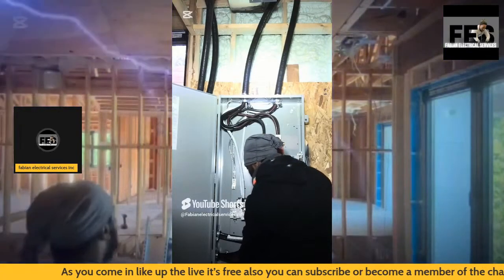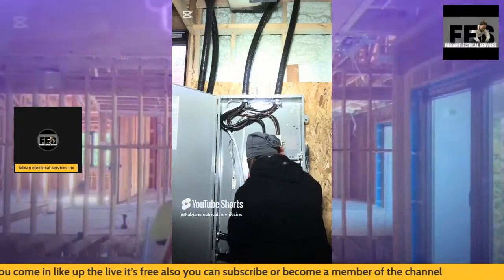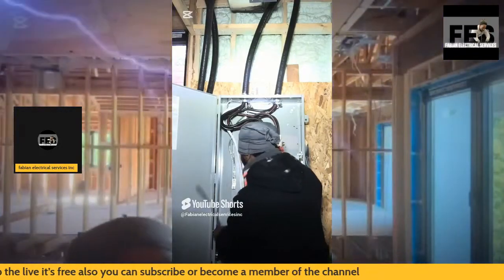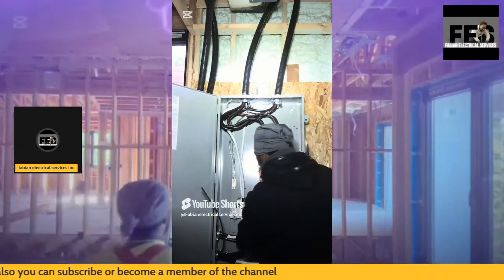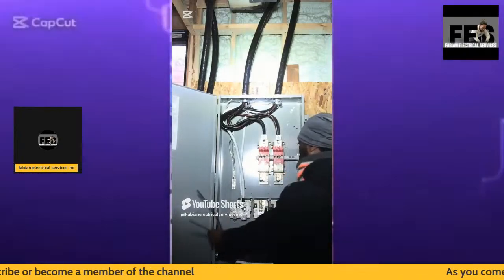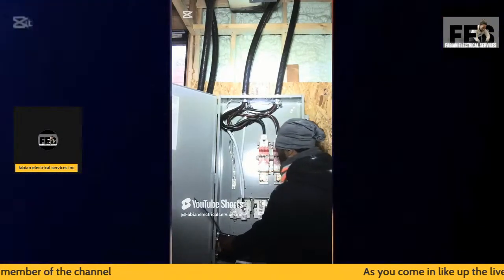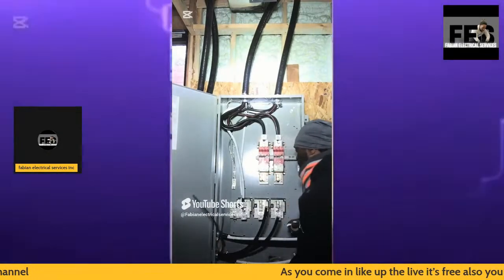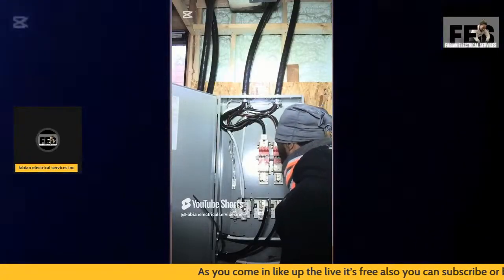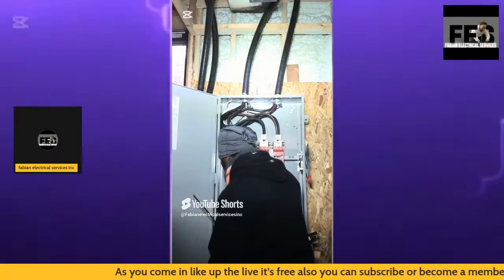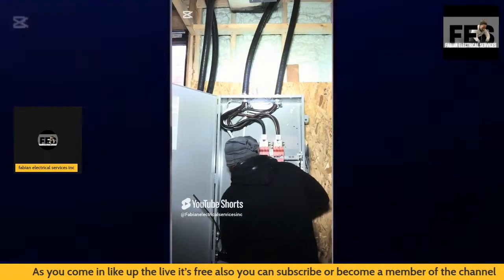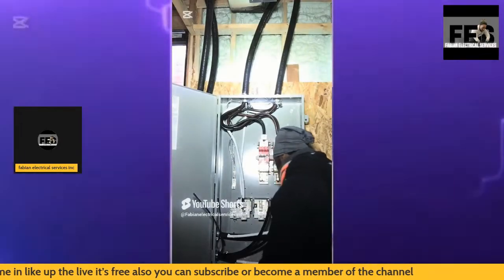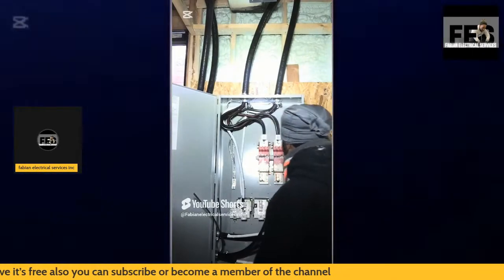The reason why this is here is because there's a code rule stating that any panel that's more than, I believe, 5 feet away from the meter base has to have a disconnect. So that's basically what happened.